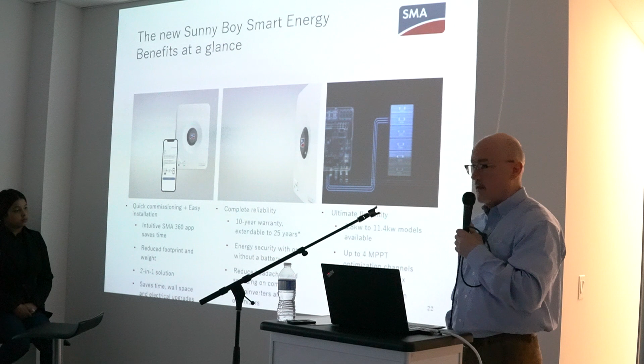We support in this product a 200% DC to AC ratio. The real issue is what we call full load hours - there's a calculation where it's basically your annual production amount, not to exceed a certain amount. It's very difficult to ever hit that number, but that's the real key, and we have a white paper on that. If you're getting into these large DC to AC ratios, our calculation tool will flag this as well if you're getting close to full load hours.